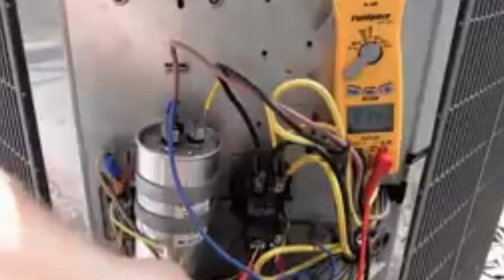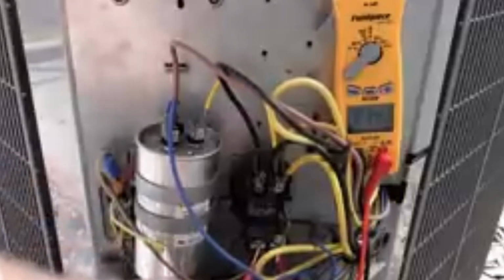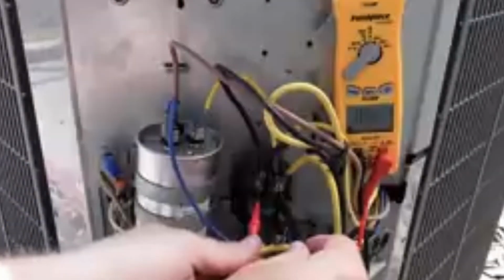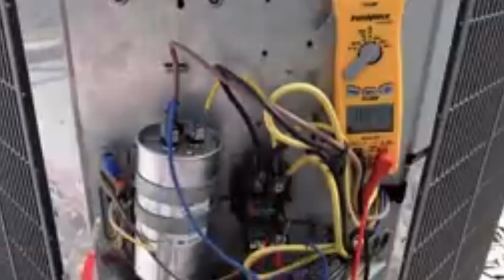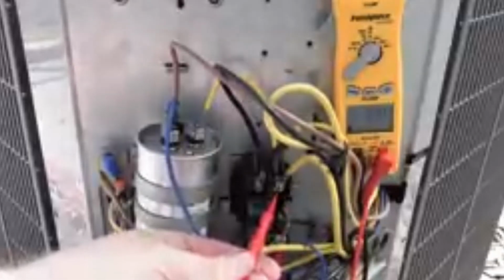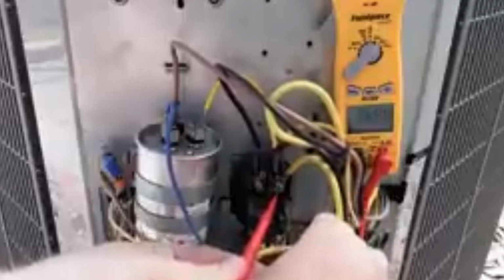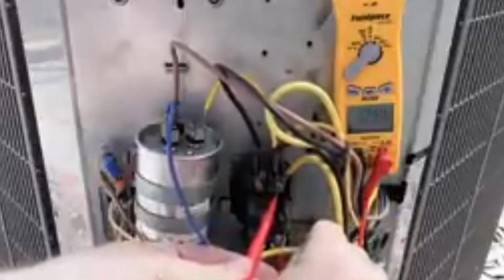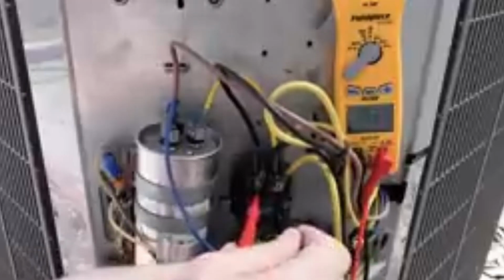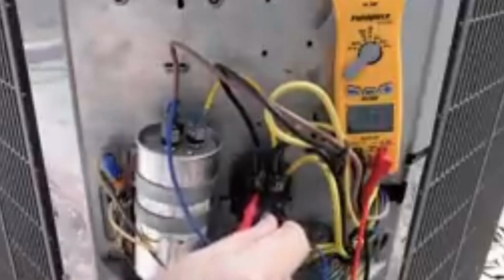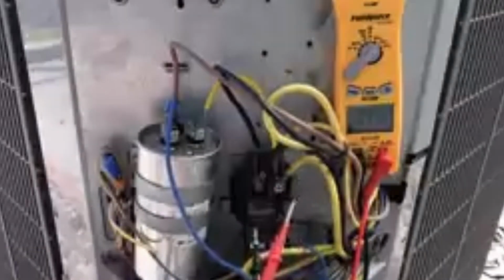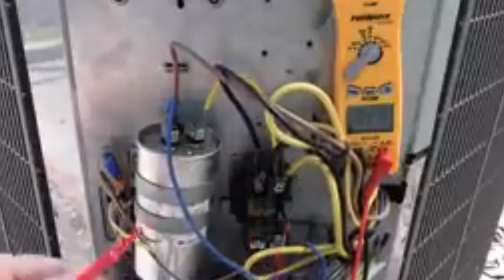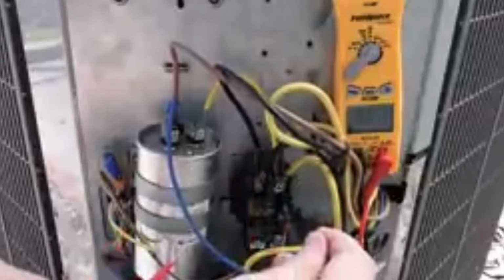So now you can see we have 214 volts at the bottom of the contactor, like we would expect, but we measure nothing at the top. But that's not true that we have nothing, and this is where the safety test comes in. If I measure from here to ground, now you'll see that I still have significant voltage present there. So this would be a diagnostic test to show that there's no potential difference across these points because one of the legs is open. But we still have 120 volts present.